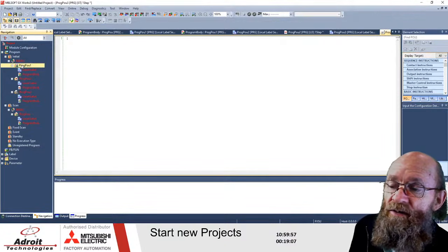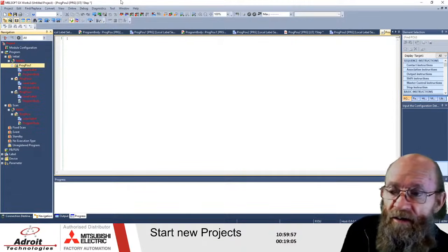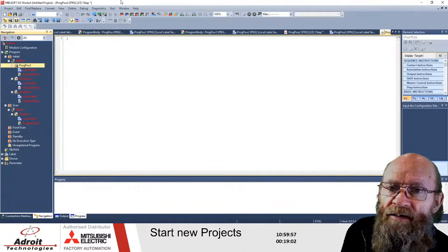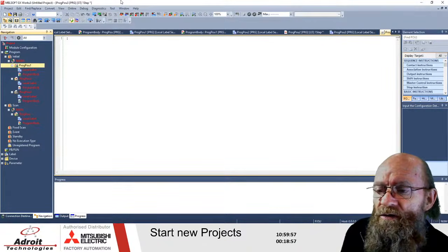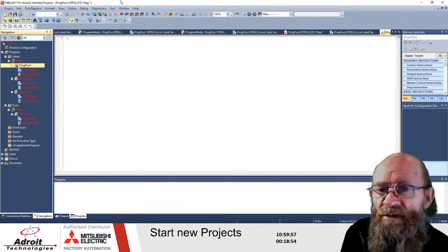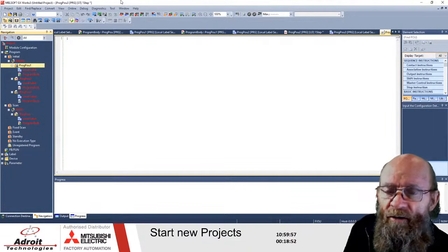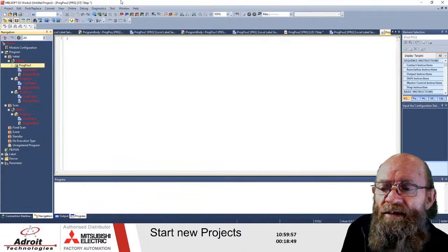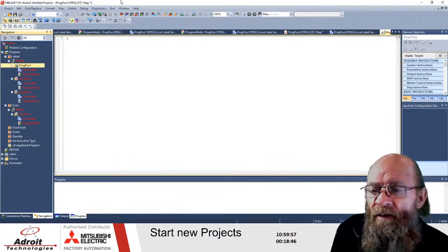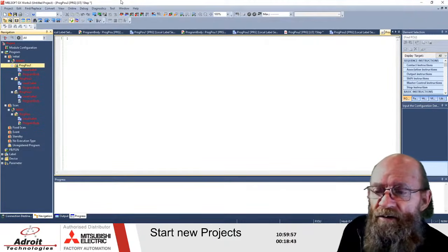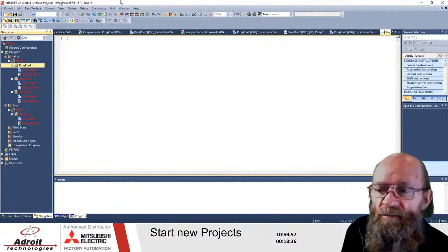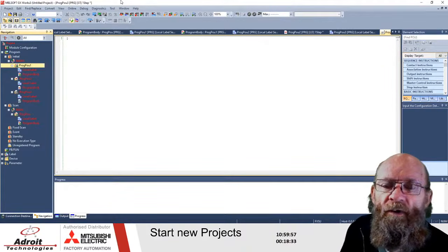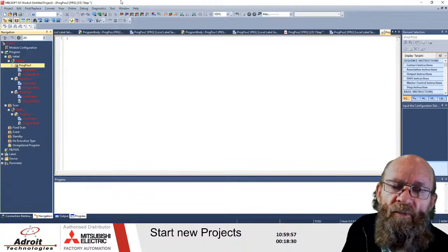on the PLC. So for instance, let's say I have counters. Natively, counters don't have retentive outputs. So what you can do is go and preset your counters before you start your program. When you've got a power up situation, you can preset all your retentive values and update your counters for your next startup. Okay, so you can maybe set values into your high speed counters, or just configure your PLC or your plant to be in a specific state.